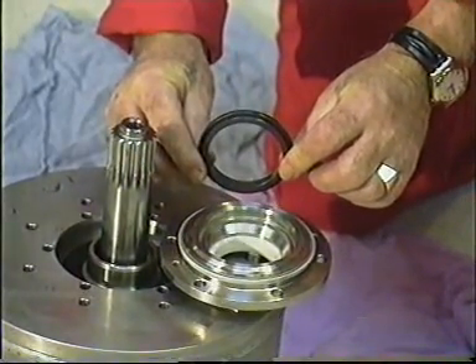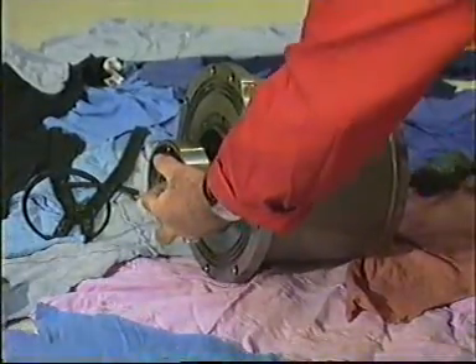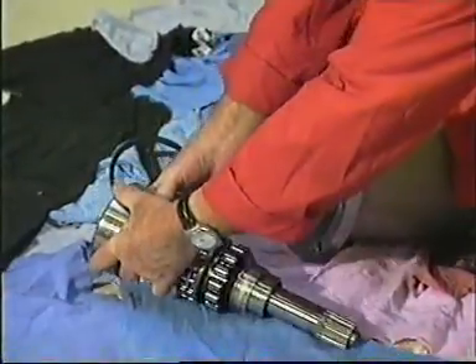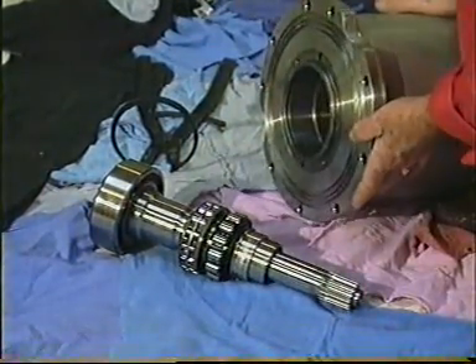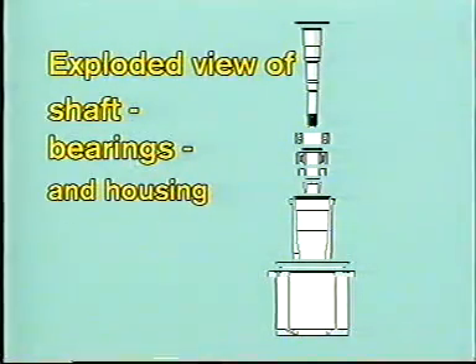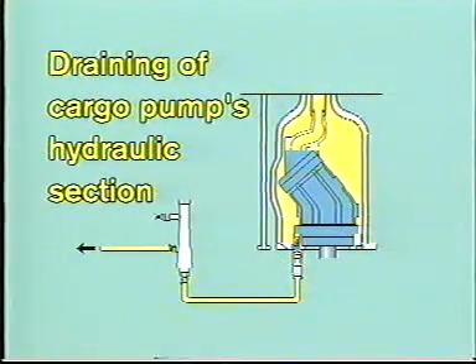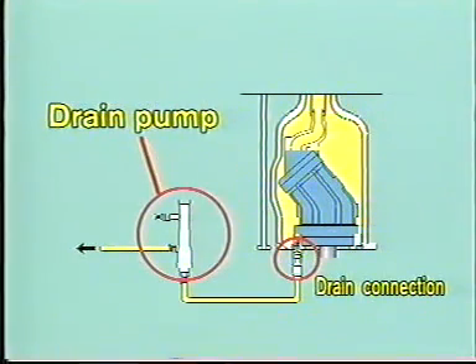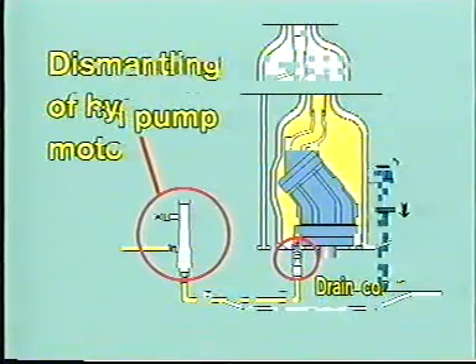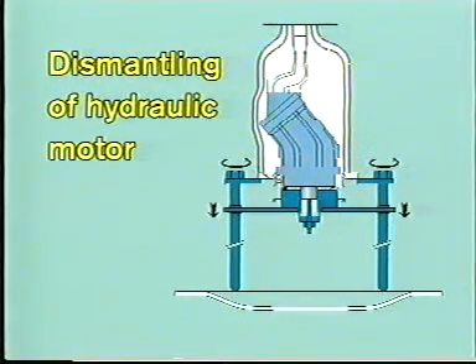Use soapy water. If it should be necessary sometime in the future to dismantle the pump shaft, ball bearings and backstop unit, this can easily be done by following the instruction in the service manual. The same applies for the hydraulic motor, but remember, before dismantling the hydraulic motor, you have to drain the hydraulic oil from the pump stack. To reduce oil spill to a minimum, use the small air-driven drain pump delivered by Framo. Then lower the hydraulic motor by using a Framo jack, and the cargo pump is now dismantled completely.